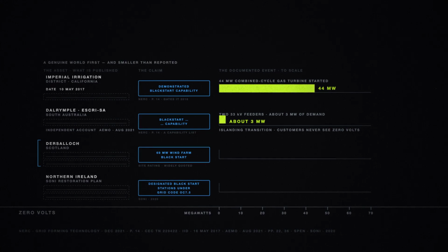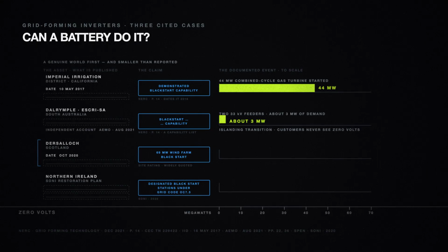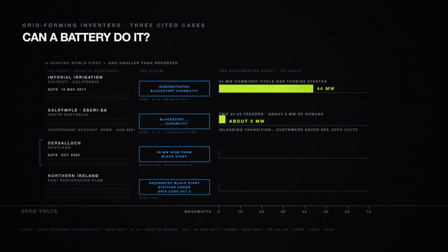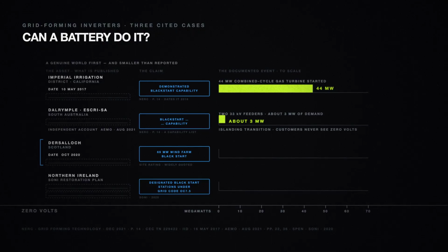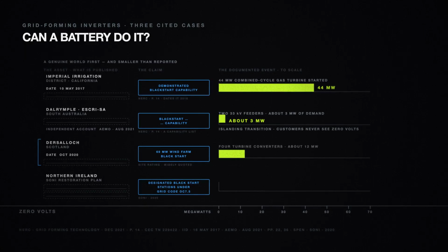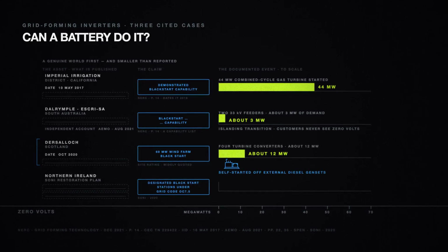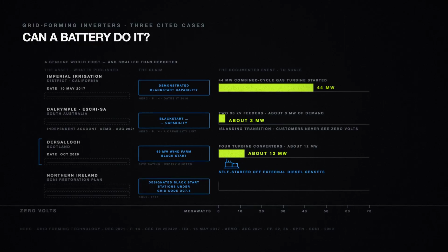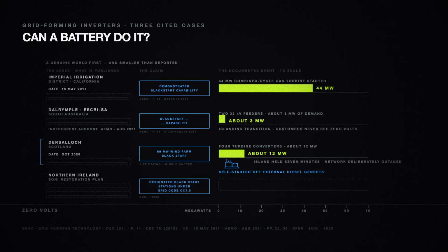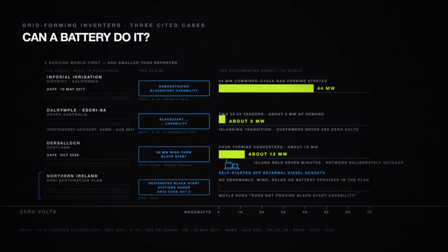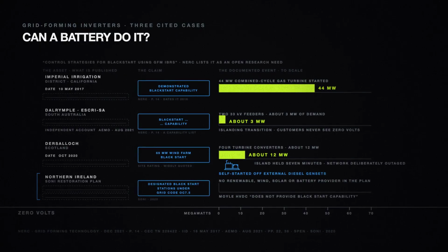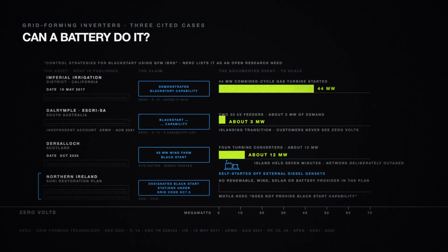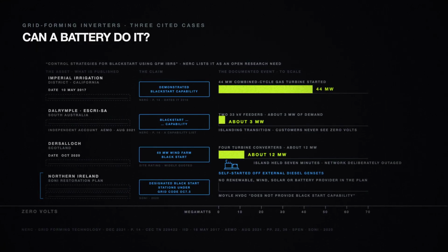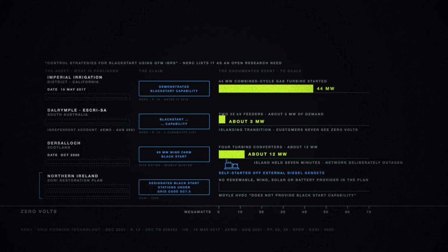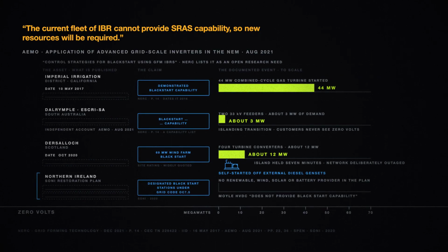Third, Dersalloch in Scotland, 2020, a genuine world first and smaller than reported. 69 megawatts is the site rating. The grid-forming algorithm ran on 4 turbine converters, roughly 12 megawatts, self-started off external diesel generators. The island held 7 minutes. On a network deliberately switched out for the trial, staff posted along the line. None of that means a battery cannot do this. The same white paper lists control strategies for Black Start as an open research need. The claim is not that the technology fails. It is that the reputation runs well ahead of the published evidence.